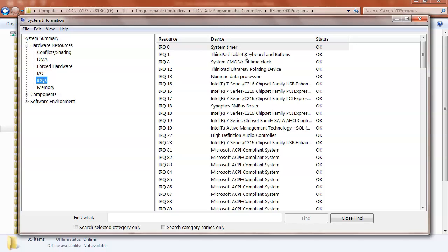We do have some extremely high priority interrupts, which usually are not available to the user at all. These are taken care of inside the PLC. These are called non-maskable interrupts. These would be like your faults. You have a major fault. I don't care what you're doing, it's going to stop everything. It's going to run a fault. It's going to turn that red light on up there, right? And it's not scanning, it's not doing anything.